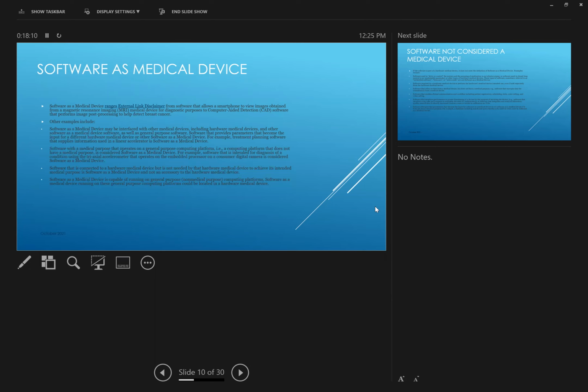It's actually taking information off the patient and then adjusting our control to adjust how that machine operates. So that would definitely be considered a software as a medical device, because it's actually taking data, making interpretation, and then adjusting the treatment to that patient. So those kinds of things would be an example of definitely a software as a medical device.